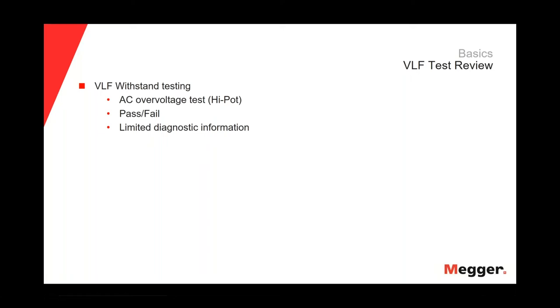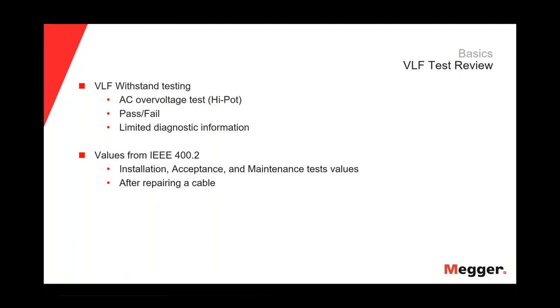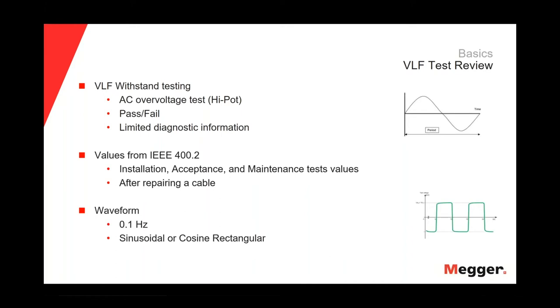It's a go or no-go test. That means that the cable will pass or will fail during the test, and the VLF test will provide limited diagnostic information, okay? We can use the VLF test for installation, acceptance, or maintenance tests, and/or after repairing a cable. And for the VLF test, we have two wave shapes, the sinus wave shape and the cosinus rectangular wave shape. And the frequency that we will use in this AC hypot test is 0.1 hertz.